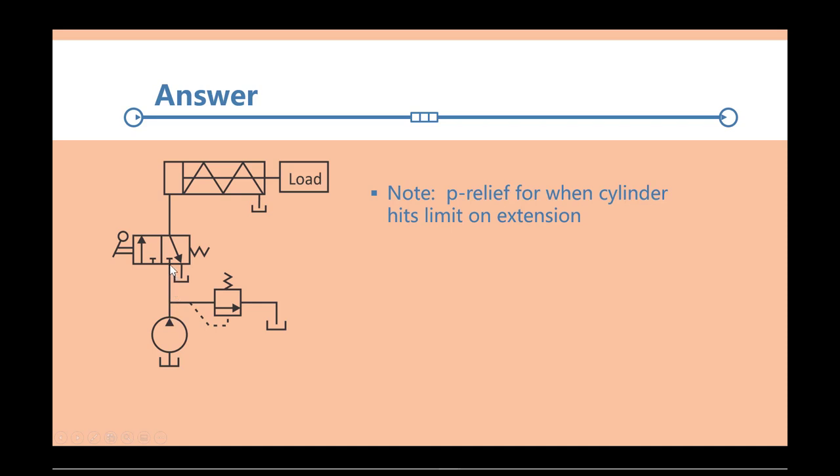You have this connection coming up here. Well, if you look at each envelope and count the number of connections to it, one, two, three, one, two, three. So that means it's a three by two valve.